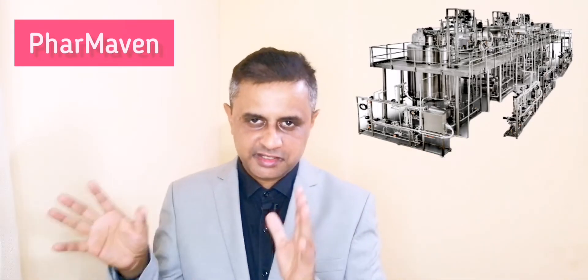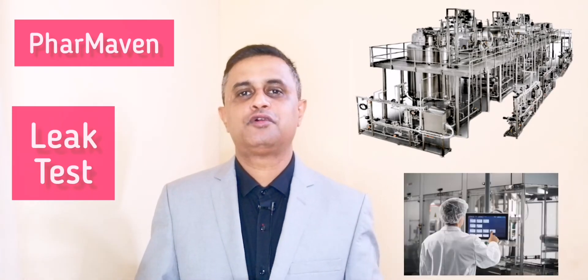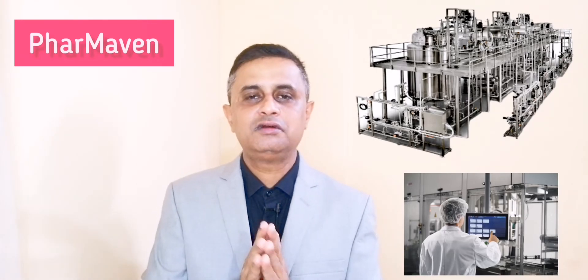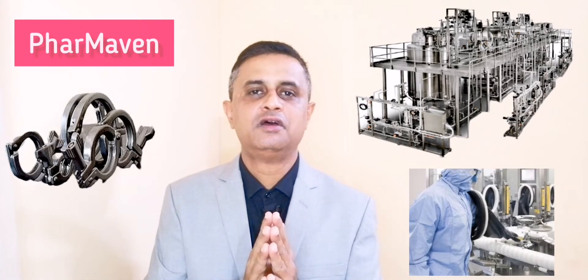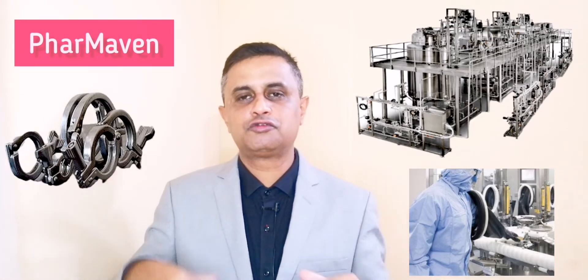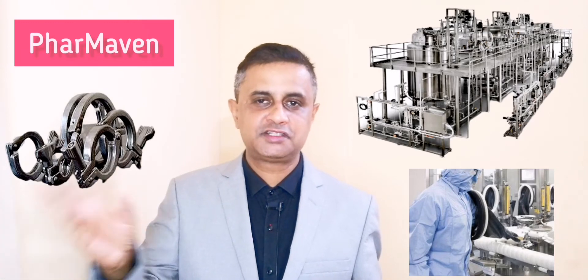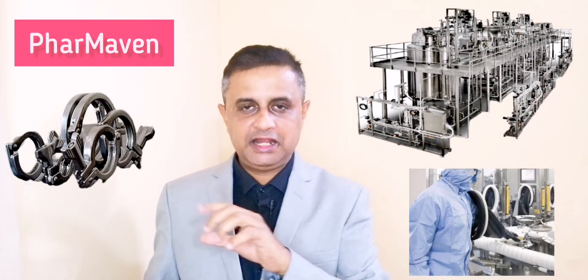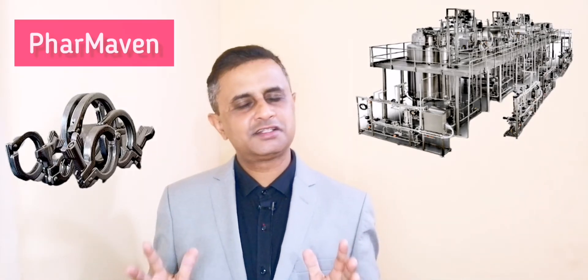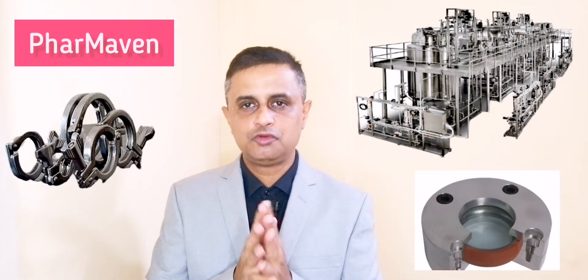In a skid system with multiple vessels and multiple connections, a leak test of the entire system is very, very important. You have to perform the leak test just before your sterilization cycle — not after any intervention. No further connections or interventions should happen once you have completed your leak test. Then go directly for processing, whether media fill or product.